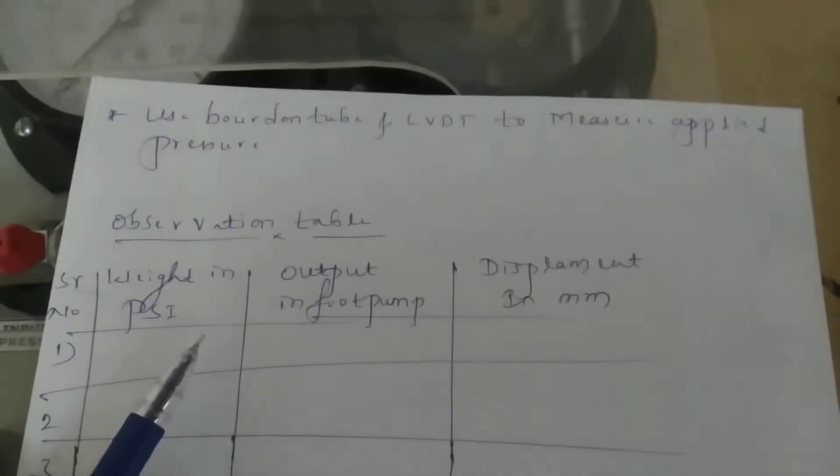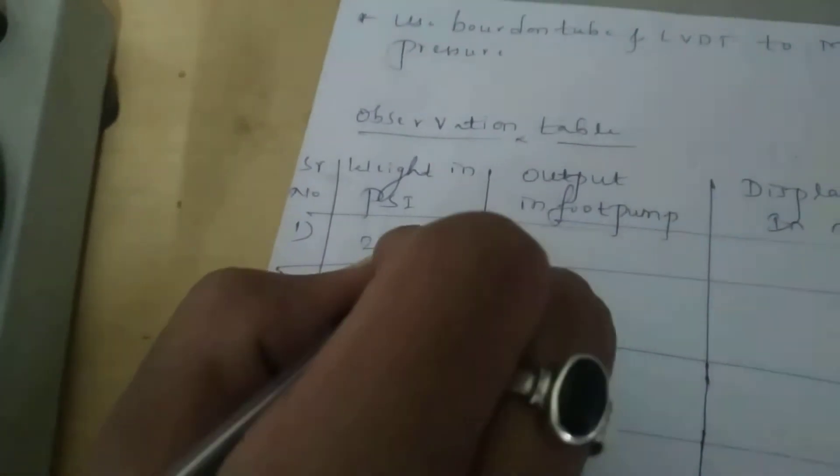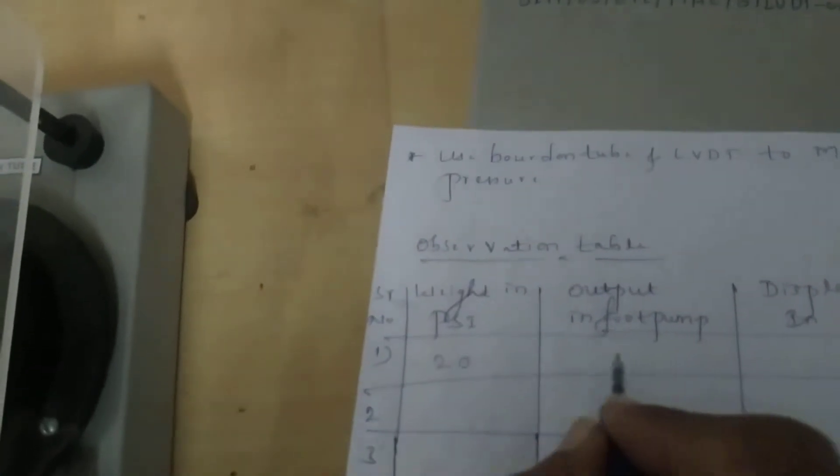In SI units, you measure in terms of kg per centimeter square. So I will apply the first reading. Applying pressure from the foot pump, you get the weight input as 20 PSI and the output reading on the foot pump gauge shows 22. Comparing these two, the difference — the error — is 2. The displacement reading is 0.06.